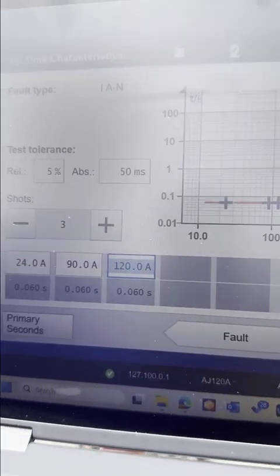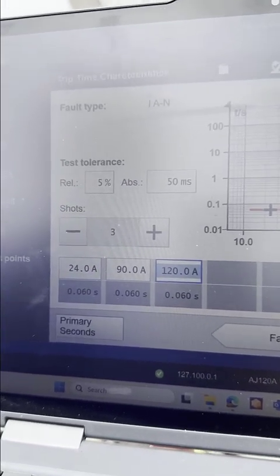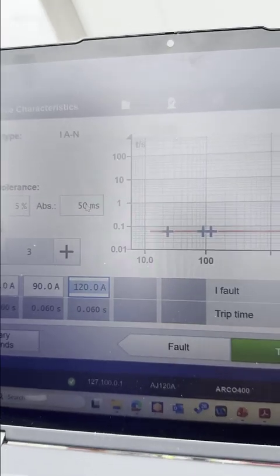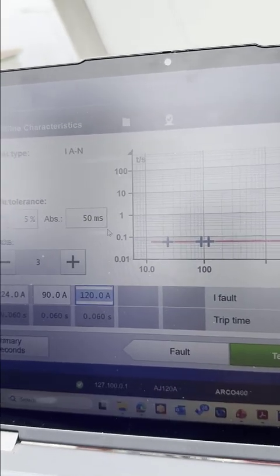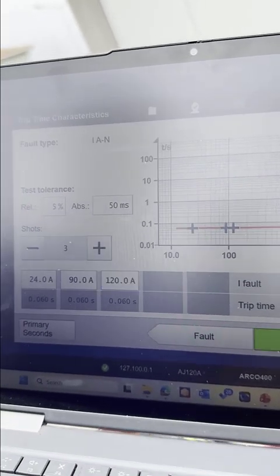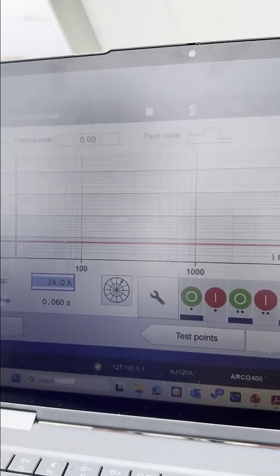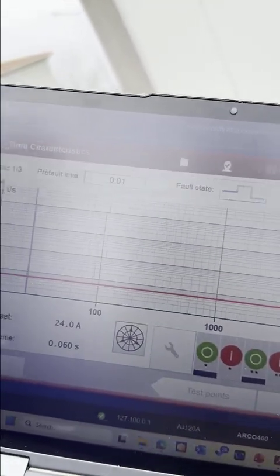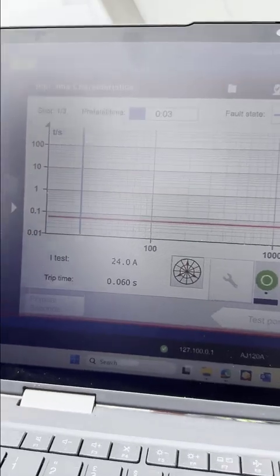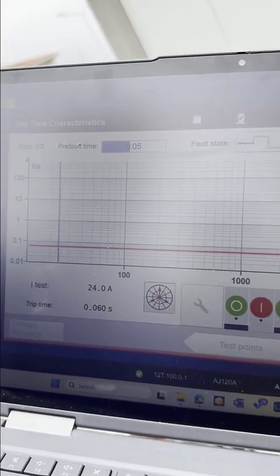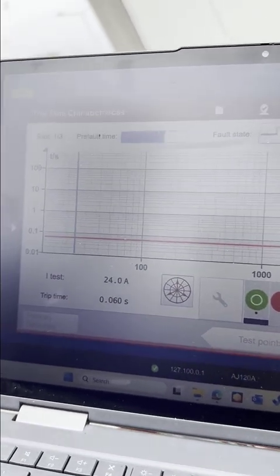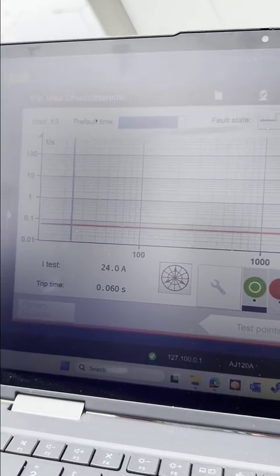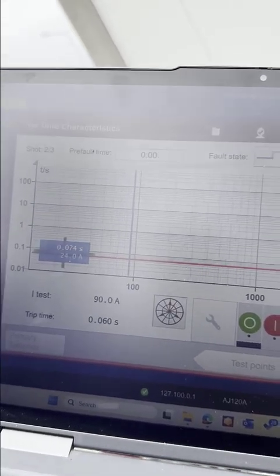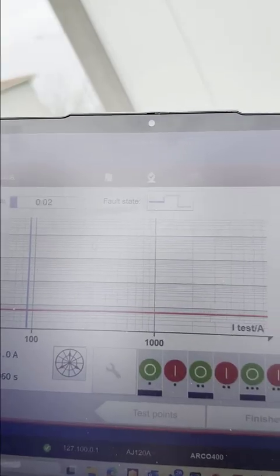As you can see from the curve here, you can specify also the relative tolerance, absolute tolerance, and the ARCO control will take whichever is greater for automatic assessment of the test results. Then you can go for test. Then you can click start. Now it's in pre-fault stage. Then it will inject 24 amp with 60 millisecond. You can see now it's 24 amp, but it's passed based on the tolerance or the allowed error bands.